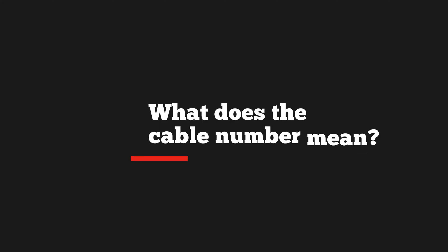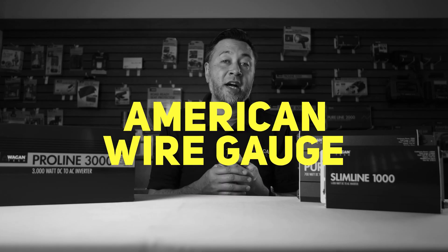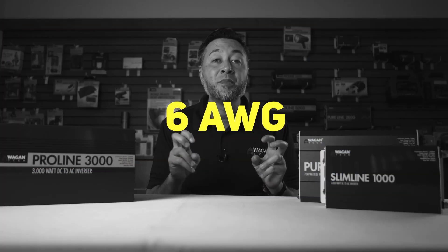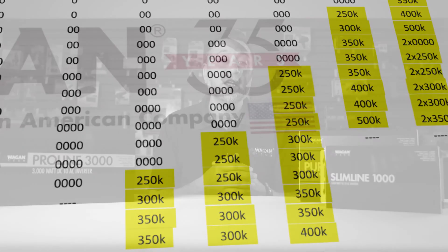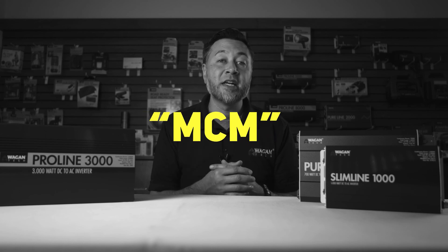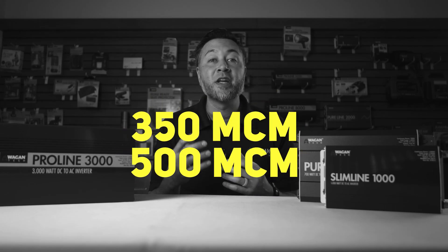Now that you've located your cable number, what does that mean? If it's just a number by itself — like 6, 4, 2, 0, 00, etc. — it represents the American Wire Gauge size, read as 6 AWG, 4 AWG, and so on, which is universally understood. If the number ends with a K designation, it is short for kcmil. kcmil and MCM cable gauge sizes are interchangeable numbers for large diameter wire cables, read as 350 MCM or 500 MCM.